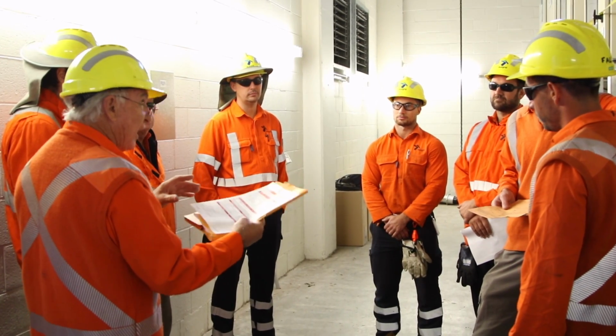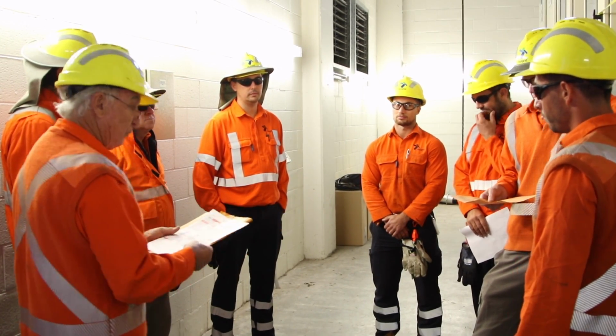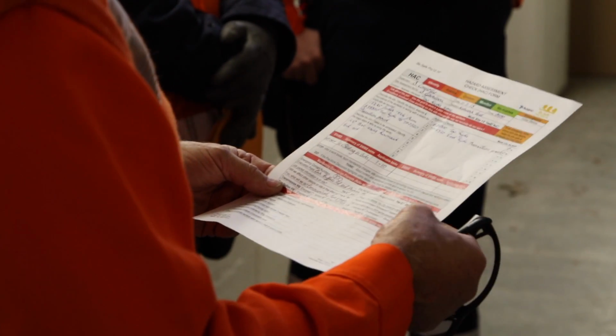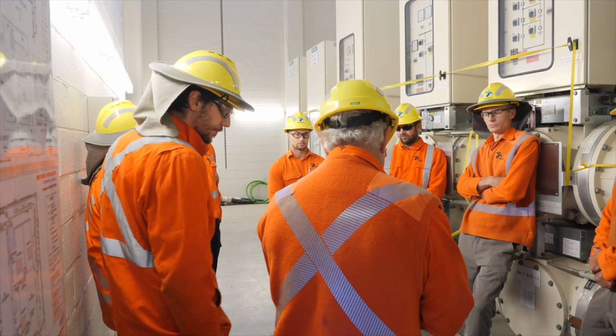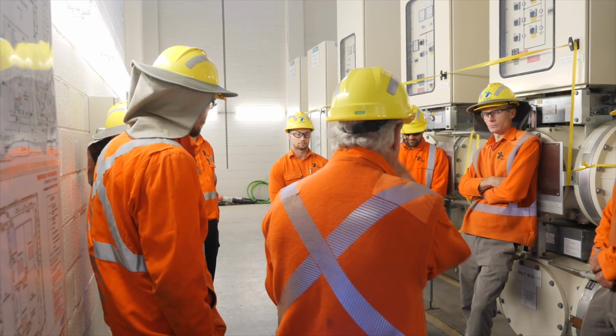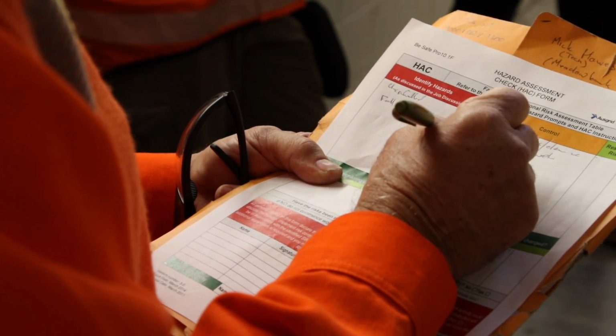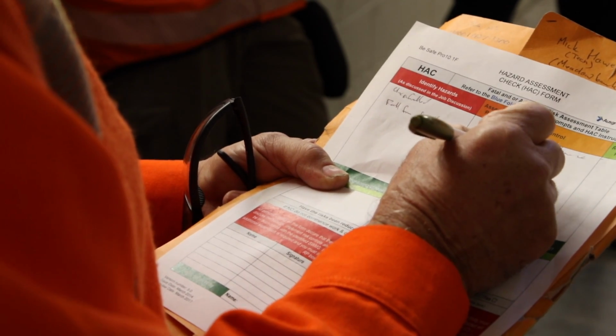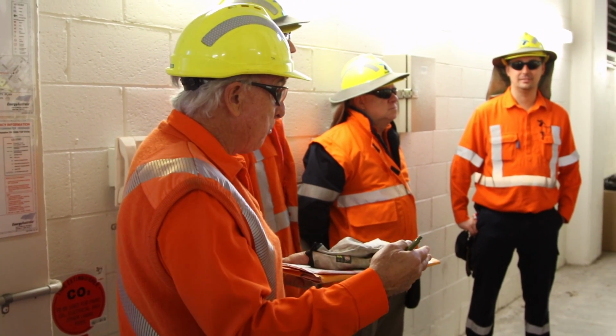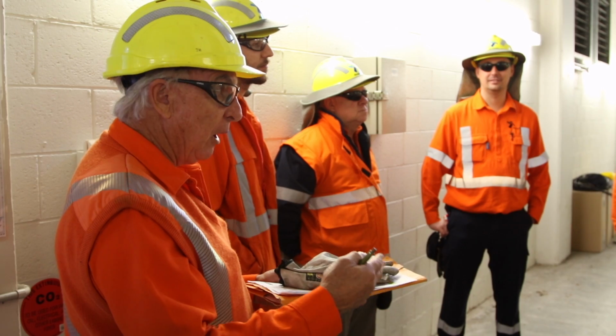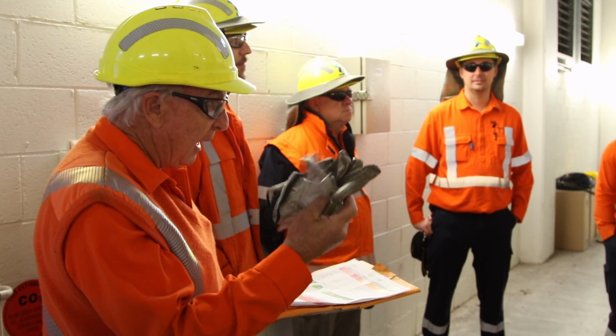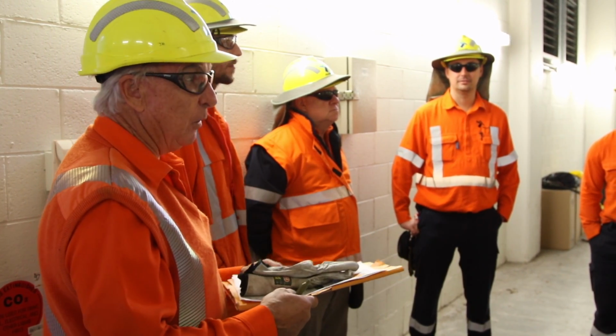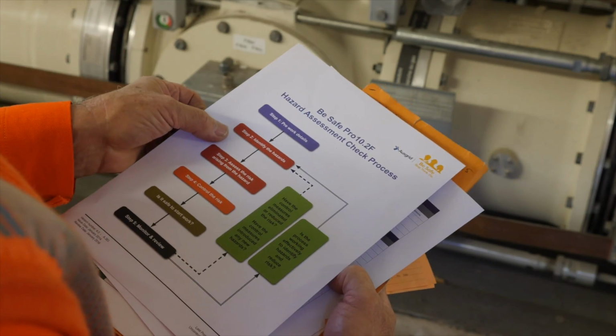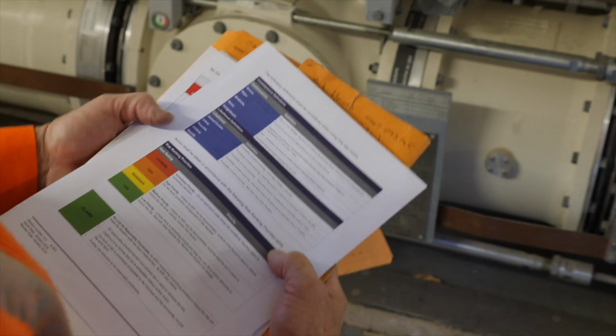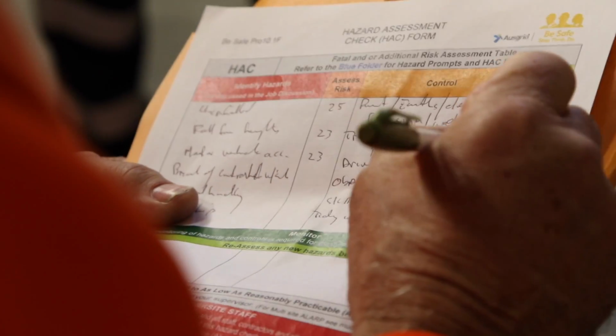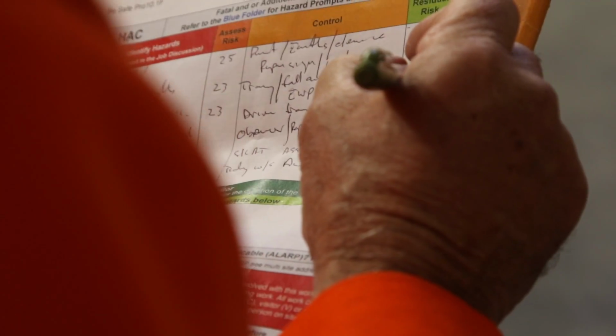At the beginning of the job, we perform the hazard assessment check in conjunction with the Safe Work Method Statement for high voltage testing in substations. Through discussion with the work group, hazards associated with the work are identified and then assigned a risk rating. Just a reminder again, we're in a zone sub, so we need hard hats, gloves and glasses obviously at all times. Controls are then put in place to manage the risks and the new risk rating is recorded. 23, and we can drop that to probably 8 or something.